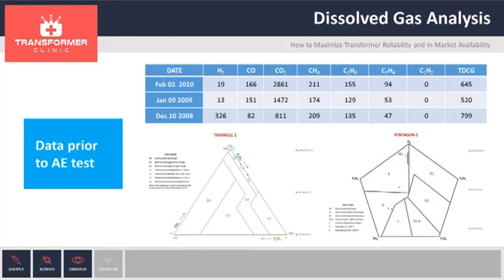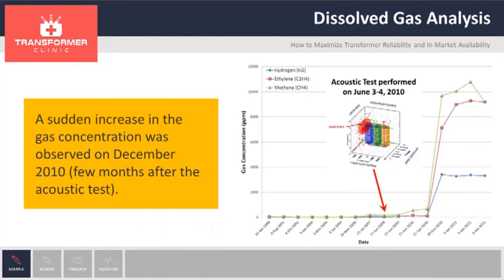We did an acoustic emission test on this unit, and we found acoustic activity detected on the upper part of the phase U coil. The test was done in June. At that point, the gases were relatively low. Based on that condition, the utility decided to keep the transformer in service. A few months later, the gases spiked and increased significantly, and at that point the utility decided to take an outage and do an internal inspection.